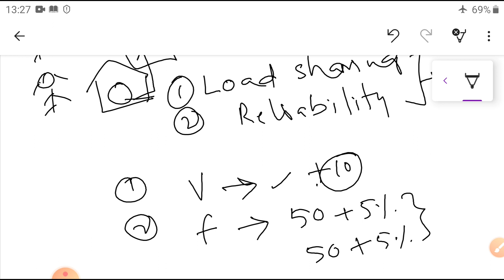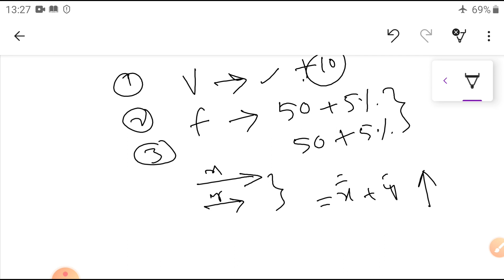What is the third condition? The phase sequence of the incoming alternator must be equal to the busbar phase sequence. That means whatever voltage is generated in one direction, the coming new generator's phase sequence should be in phase with it, both should be in phase. Then, if this is x and this is y, the resultant is equal to x plus y, both additive, which is what is required. So these are the three conditions - voltage, frequency, and phase sequence - that must be satisfied before connecting a new system in parallel with the existing system.